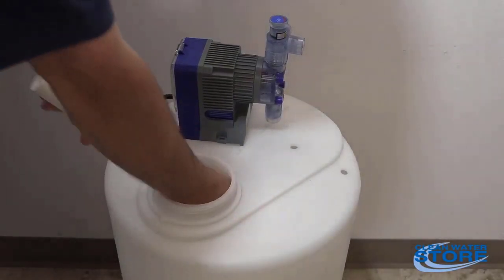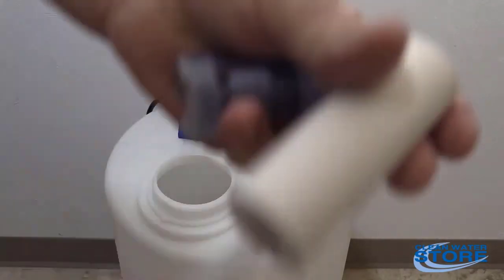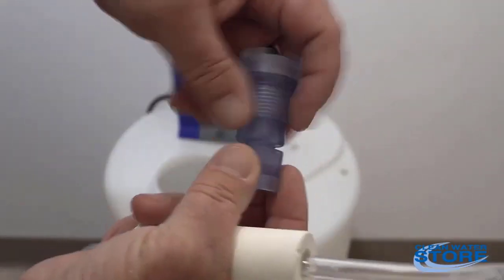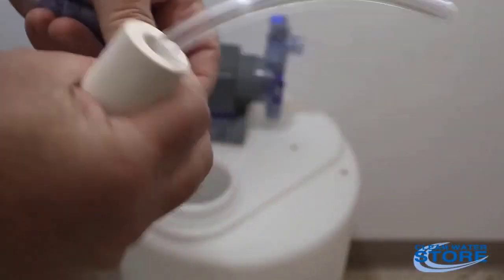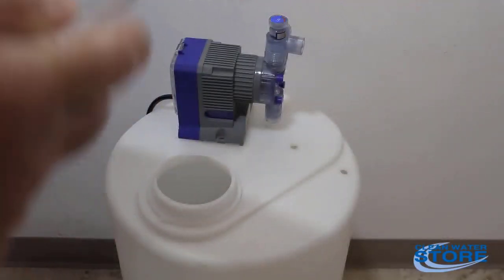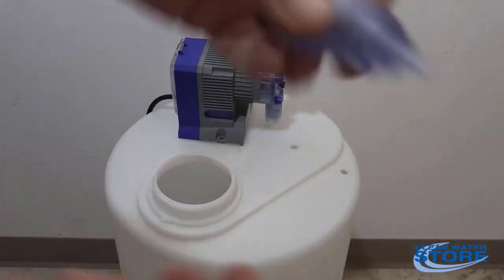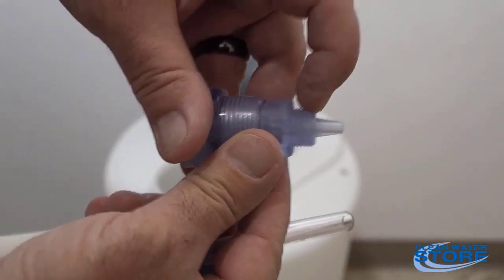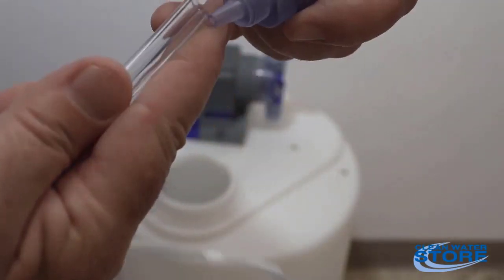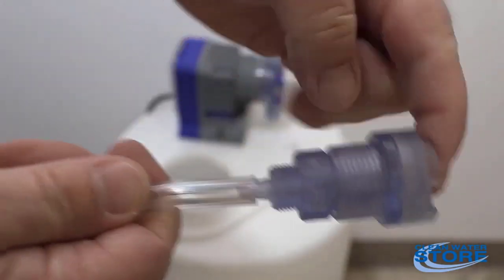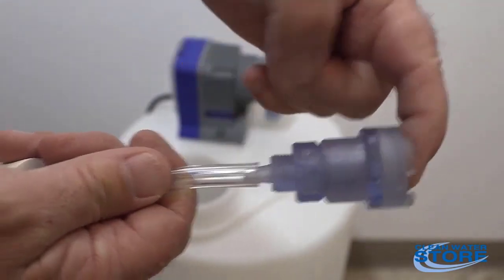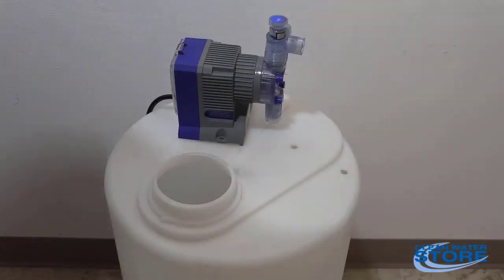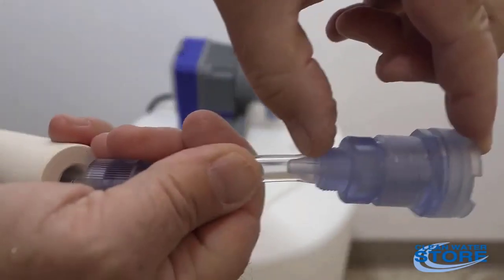We're going to put our weight on through the hose. Then we're going to unthread this little cap here, slide the cap through. You have this little barb here. The hose needs to come all the way up to the shoulder here. These won't stay primed if they're not done properly, if you have air leaks through here. This is not correct. You want to make sure you keep this all the way up to the shoulder like that.